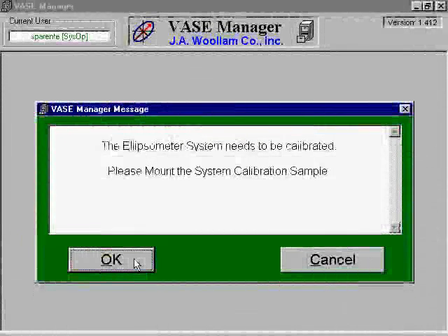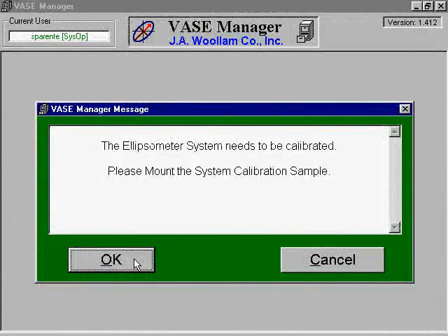If you see a screen telling you that the ellipsometer needs to be calibrated, then you will need to perform a calibration before continuing. The calibration will either begin automatically as the system senses it needs to be calibrated, or you can choose calibration from the software configuration screen.